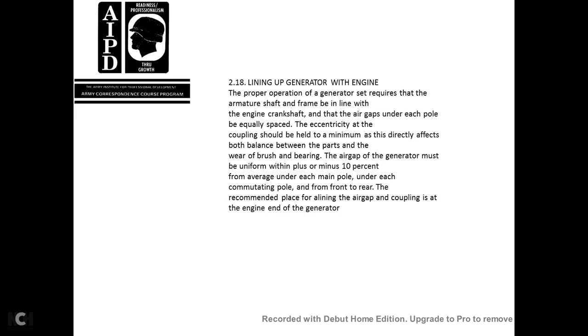2.18 Aligning the generator with the engine. Proper operation of the generator requires that the armature shaft and the frame be aligned with the engine crankshaft. The air gaps under each of the poles should be equally spaced. The eccentricity at the coupling should be held to a minimum, since it directly affects both the balance and the wear of the brushes and bearings. The air gap of the generator is to be uniform within plus or minus 10% of the average under each main pole and under the commutating pole, from the front to the rear.